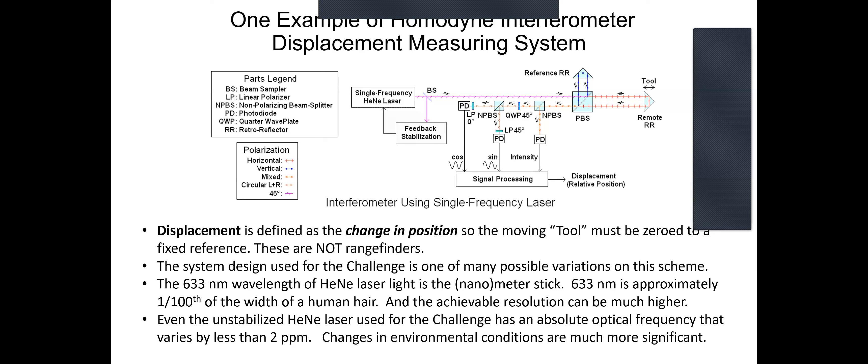But the environmental conditions are much more significant. For example, one change of one degree centigrade is a change of one part per million, 2.5 millimeters of mercury is one part per million also. So strictly speaking, we should be keeping track of that, but we're going to ignore those minor details.